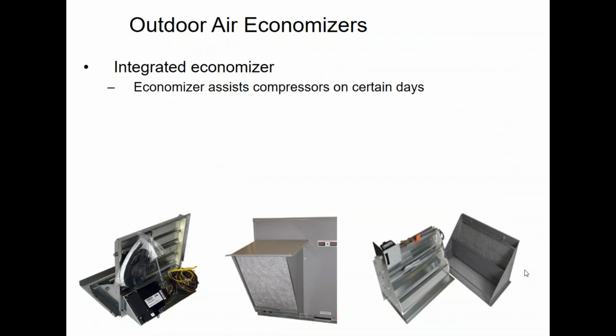when I have an outside air economizer, I also have to think about building pressure relief. I have to have a way for air to get out of the building. If I'm going to suck all this extra air in, it's got to leave somewhere else. On small, simple systems, that's typically done with a barometric relief damper. On larger systems, we typically do it with a power exhaust.